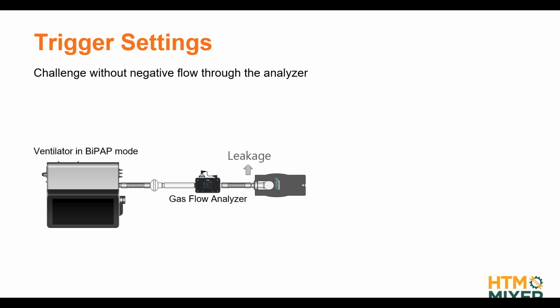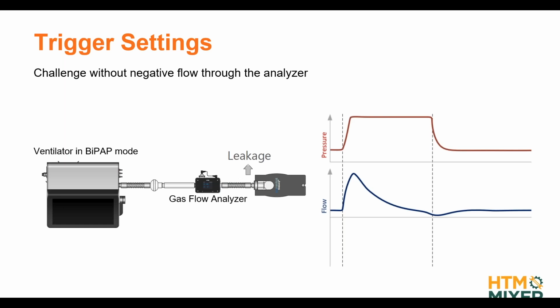Okay, so this is an example of a ventilator in a BiPAP mode, and in this setup we have a leakage at the test lung. So here is our analyzer, here's our test lung, and let's consider we have a leakage here that simulates a typical non-invasive patient interface, a mask with a leak, for example. The ventilator is going to apply pressure, volume fills up the test lung, and then it releases pressure, and the volume actually goes out the leakage and does not go back through our analyzer. That means the flow through our analyzer is never going to be negative, and unfortunately our previously discussed default trigger settings are no longer going to work. Okay, it can happen that you get into such a situation.